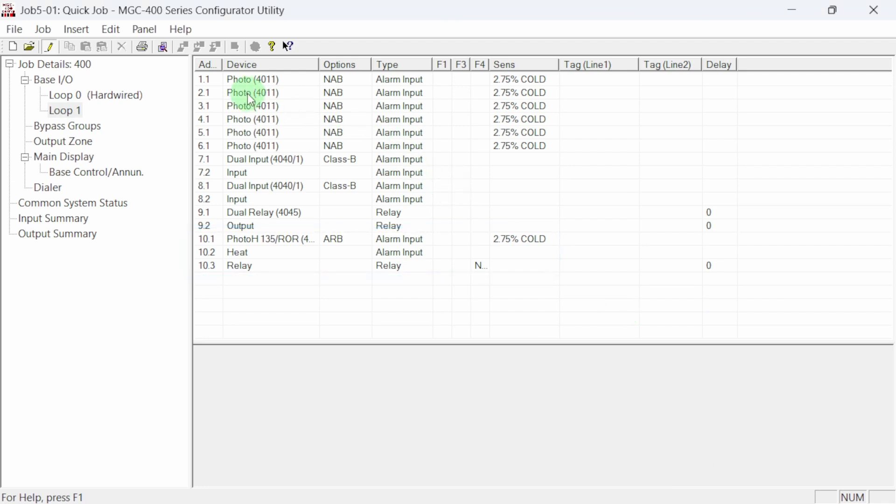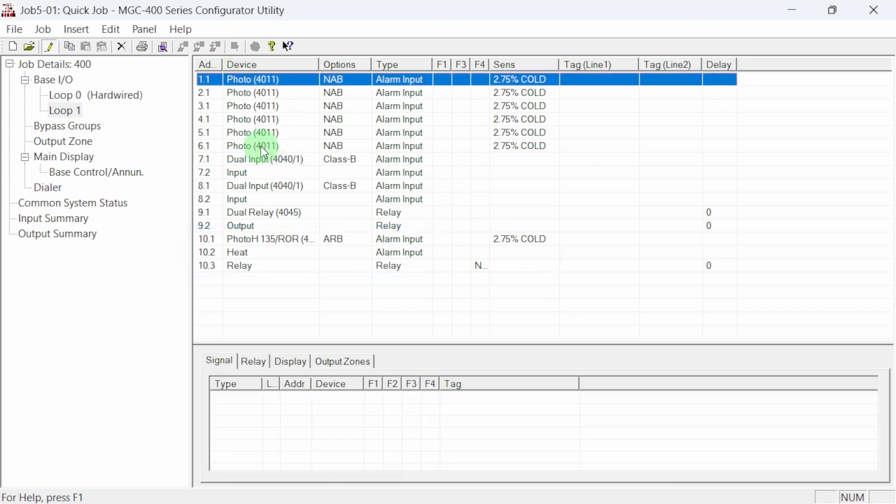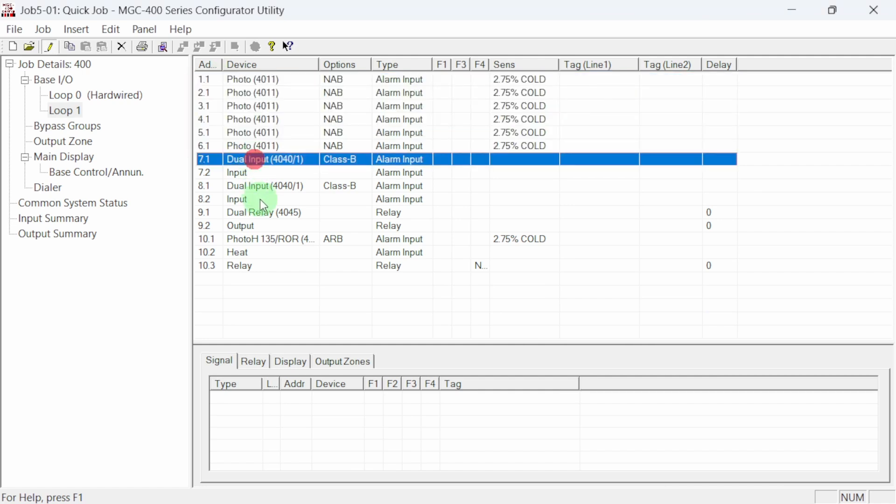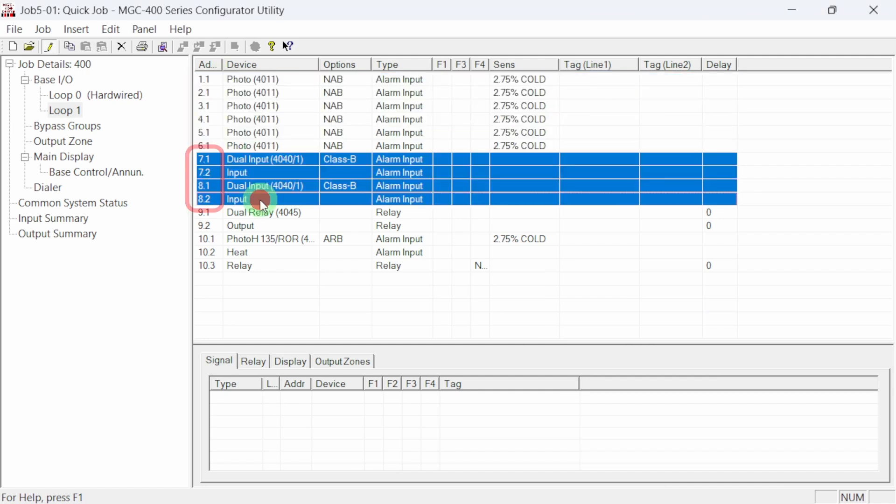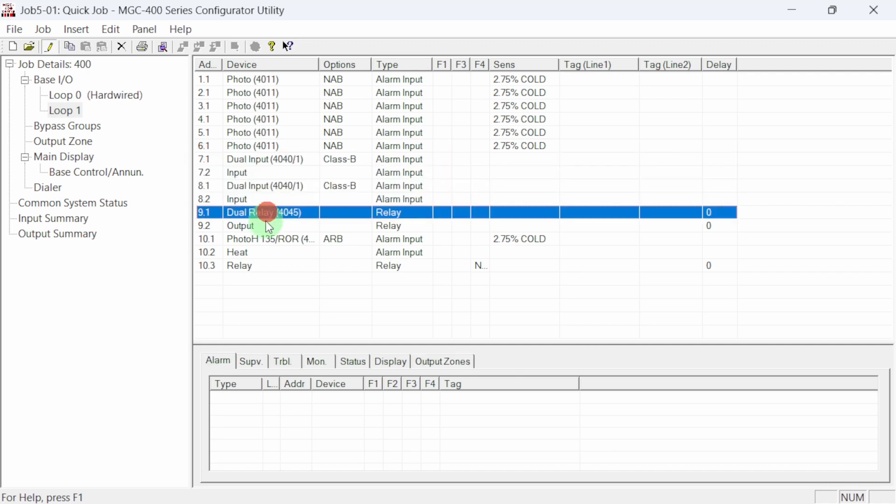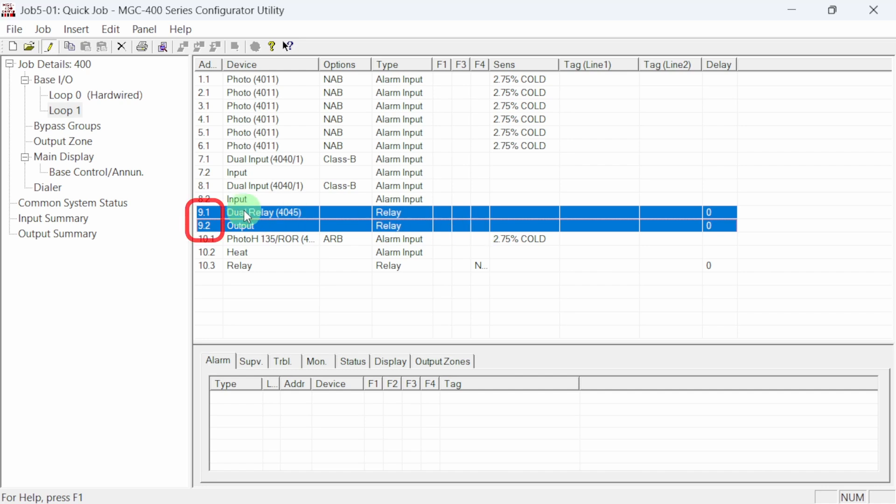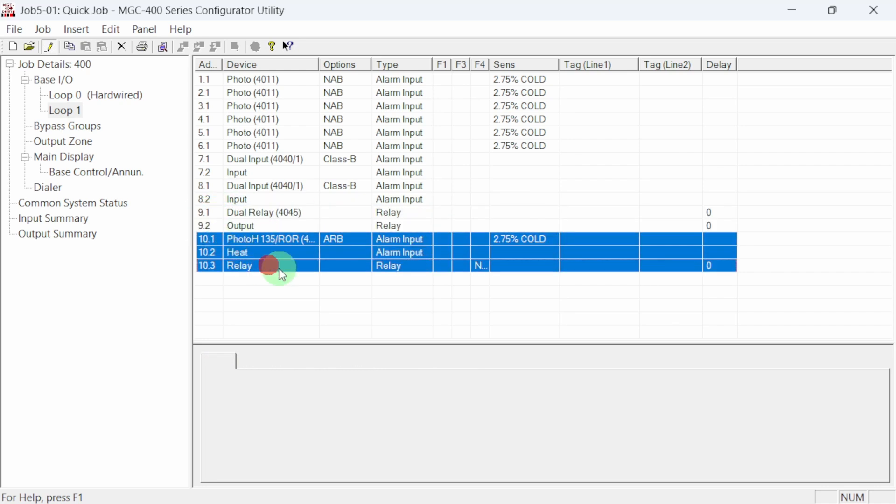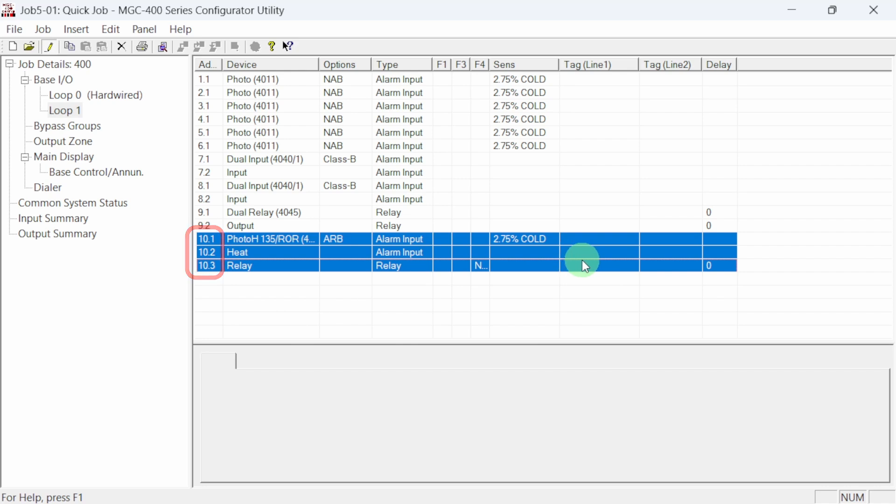Our job has six photoelectric smoke detectors with device addresses 1.1 through 6.1. The dot one indicates the primary address setting. We can see our two dual input modules with the dot one primary and dot two sub addresses. Here is the dual relay module with relay contact one having its own point and relay contact two having the sub address. The dual sensor at address 10 has three points. The primary is the photoelectric smoke sensor, the dot two sub address is the heat sensor, and the dot three sub address is the relay contact in the addressable relay base.